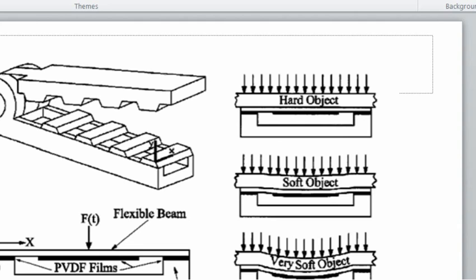Several piezoelectric elements were arranged in a 3x10 array pattern and covered by a protective layer made from silicone rubber. The whole array was designed for measuring tissue palpation force up to 15 Newtons. Small size and low cost make it attractive for MIS applications that require low mounting space and disposability.